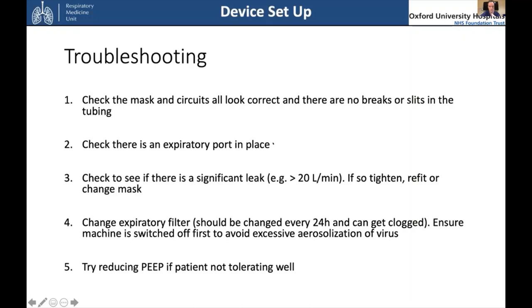Check you've got an expiratory port in place - that's important if you've got the non-vented setup. Some centres are using the normal devices with holes in them. The way to tell is you look at the actual mask itself: if it's got little holes in it, then it's a vented mask and doesn't need the expiratory port. If there's no holes in the mask, then it's non-vented, and you need to have the expiratory port in place, so make sure that's there.